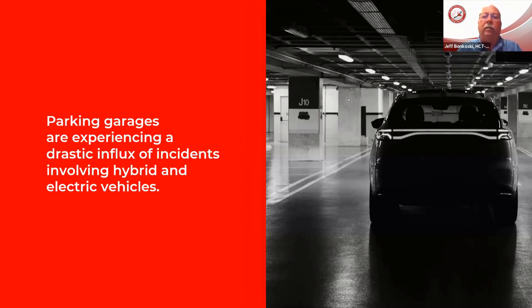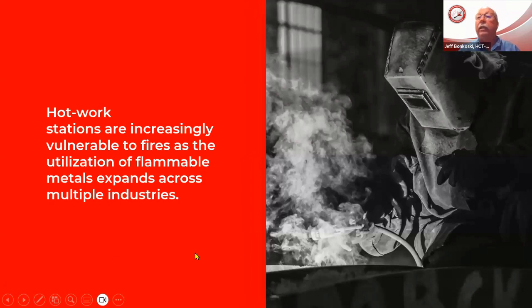We're putting the charging stations in, but not doing anything else to help with the increasing fire load in these structures. Looking at hot work in plants and facilities, we're using combustible, flammable class D metals because they're lighter weight and stronger. If we use plain water in these suppression systems when class D metals are present, we're only creating another problem - we can end up with huge explosions and molten steel flying throughout the facility.